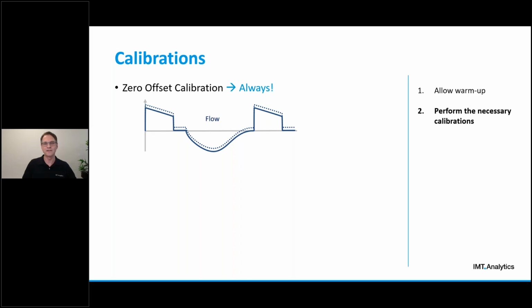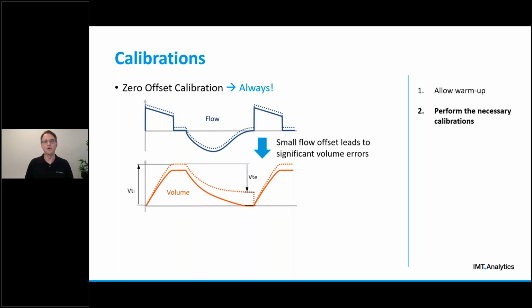As you can see in this illustration here on the slide, particularly an offset on the flow measurement must be avoided as it amplifies as an error in the volume calculation, because volume is actually the mathematical integration of the flow signal over time. So if you have an offset on your flow signal, it's going to amplify over time in your volume measurement. Then second point here, calibration of an oxygen sensor if you are using one. Some gas flow analyzers have one built in, some have a separate module for that. So that oxygen sensor should be calibrated as well. And lastly, there might be peripheral sensors that you are using that need calibration as well. So for example, this could be an anesthetic gas concentration sensor that requires a zero offset calibration too.